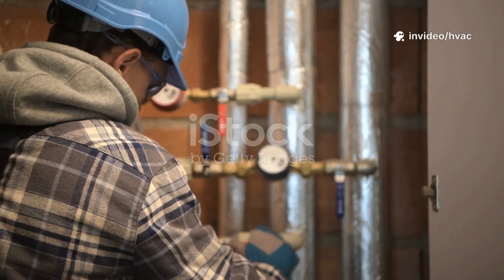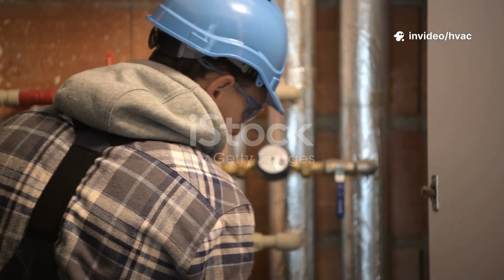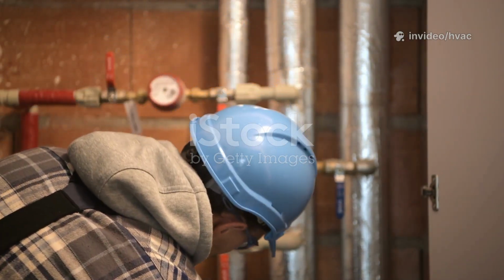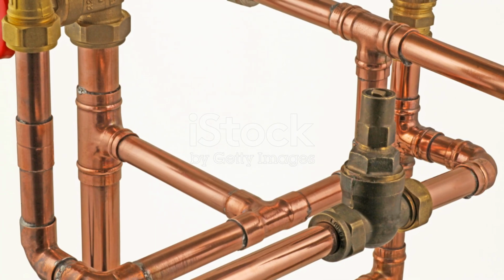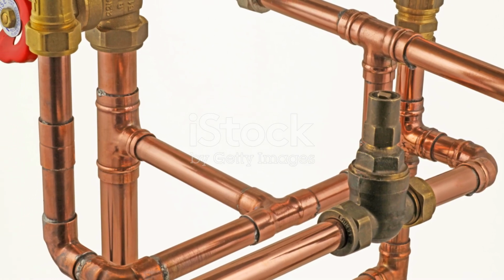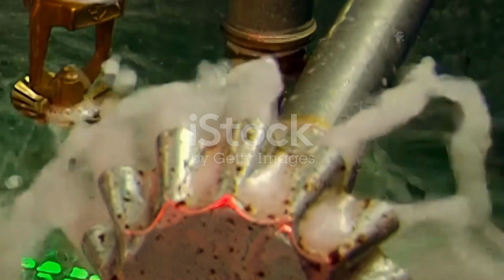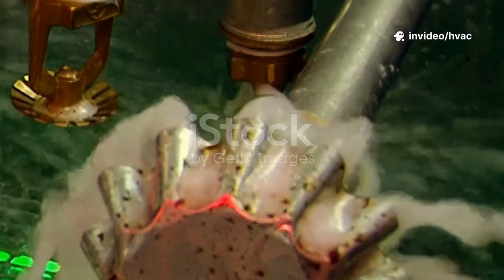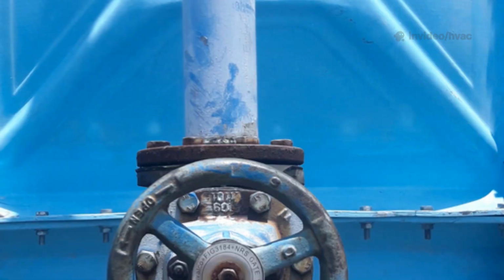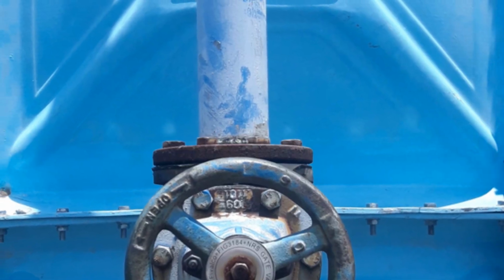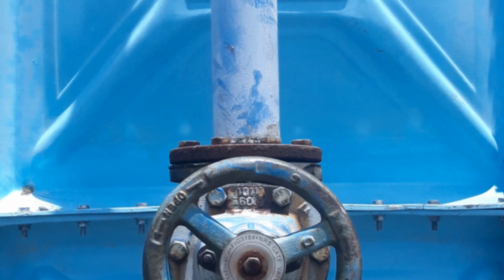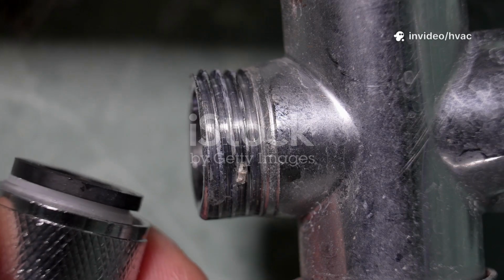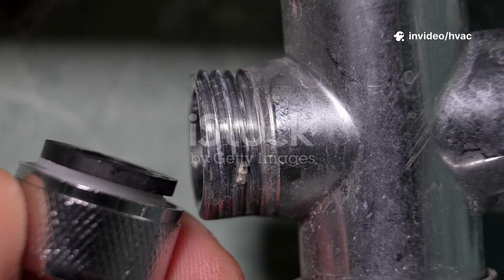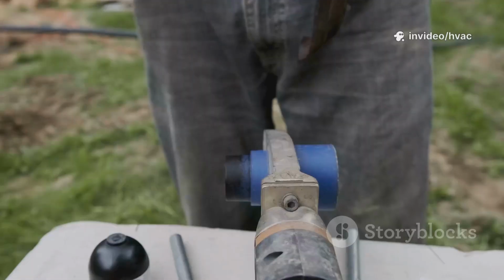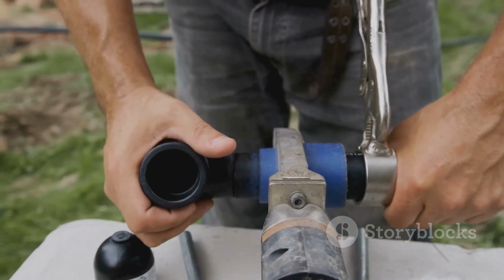Proper installation is crucial for a PICV to perform as intended. One of the most important considerations is the valve's placement in the piping. The PICV should always be installed on the return pipe coming out of the heating or cooling coil. Placing it on the return side helps protect the valve's internal diaphragm from the extreme temperatures of the supply water, which can really prolong its life. Additionally, it's essential to install the valve with the arrow on the valve body pointing in the direction of the water flow. Installing it backward will prevent the valve from working correctly and could even cause damage to its internal components. This is a simple but very important step to follow.